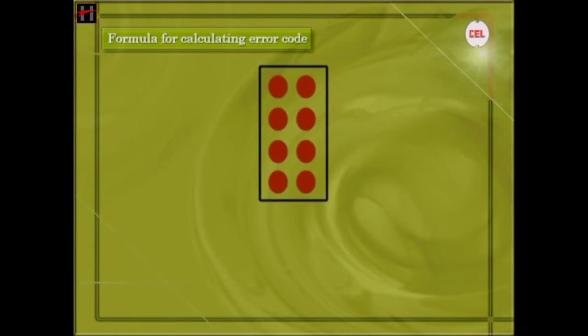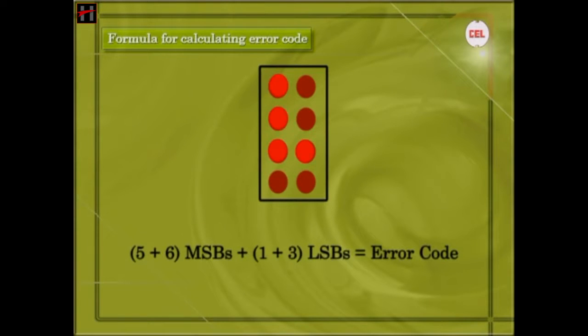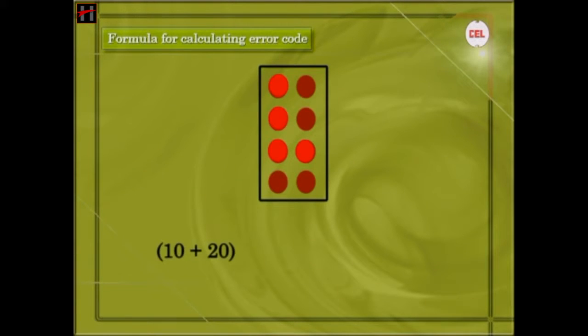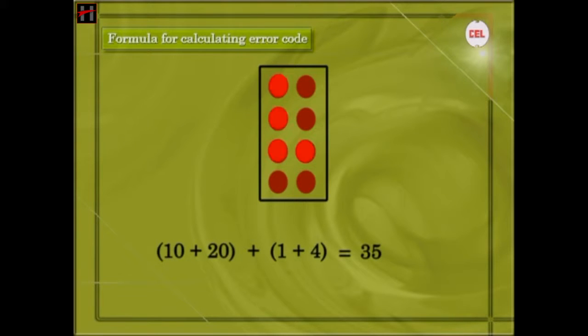Now if LED numbers 1, 3, 5, and 6 blink, then the total values assigned to these LEDs will be added to get the error code. For example, 10 plus 20 plus 1 plus 4 gives 35. This means that error number 35 has occurred in the system.